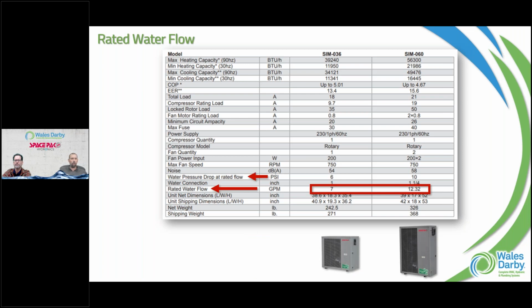The next important one there is your water pressure drop. That's the pressure drop through the outdoor unit, which is quite high on some systems, right? So we got 6 PSI. We have to convert that when sizing a circulator, which the Taco catalog has in there. How do we figure out the pressure drop, or the head, that I need to design around, as well as the GPM? Because we give you PSI, we take the PSI and multiply it by 2.31. That tells us the feet of head. So it's going to be about 23 feet for the SIM 60.